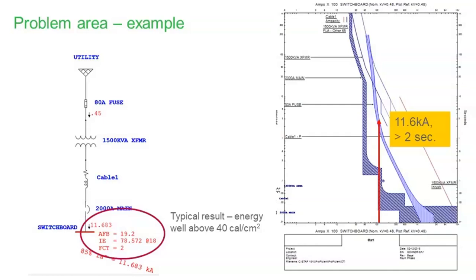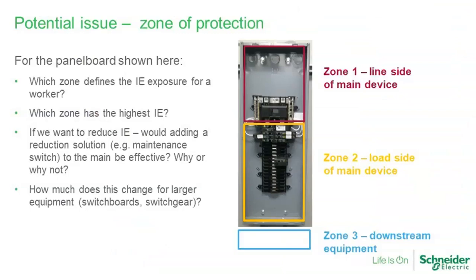One thing, you may have noticed I've got a main breaker in this switchboard over here on the left, the 2,000 amp main. Over on the right, this light blue curve, that's the curve of the fuse, the utility fuse, but then I've got the circuit breaker there as well. But how come I ignored that? Why did I go up and look at the fuse instead of stopping there at the circuit breaker at 0.2 seconds rather than going to 2 seconds, whatever it would be? Well, that's where one of the learning objectives we talked about was looking at how equipment construction might affect arc flash levels. Just one more slide to show you before we get into solutions, I promise.